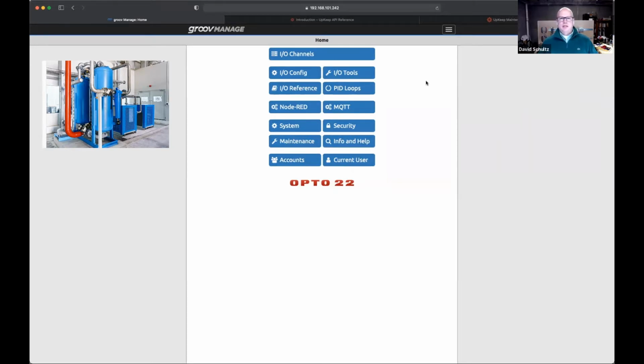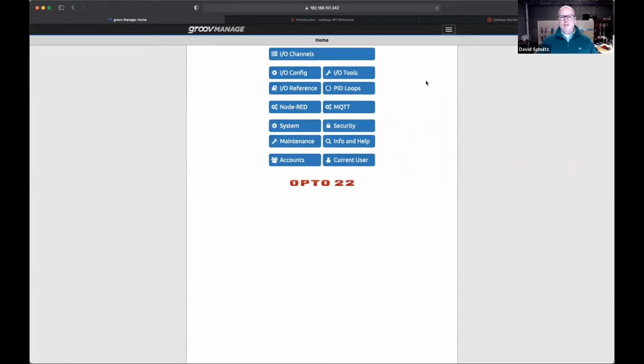What I'm going to use is an Opto 22 Groov RIO, which is designed to do remote IO. We're going to monitor a vibration sensor on this compressor. That's the example I have here, and that's going to give us a 4 to 20, so an analog input. Then we're also going to monitor a discrete input through the filter on an air compressor as well. There's an after filter, and eventually it does get plugged and you're going to have to go in and change it. So we're going to create a work order based on the high vibration, as well as one on a high pressure drop.